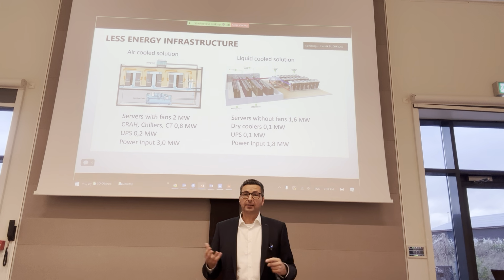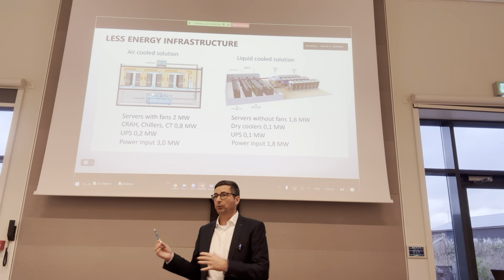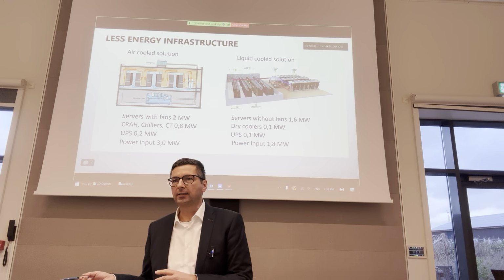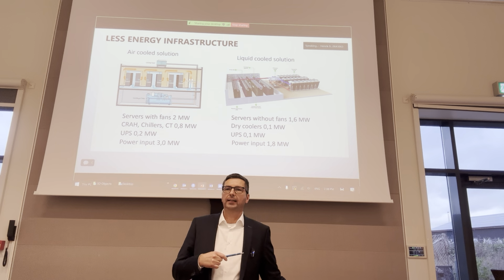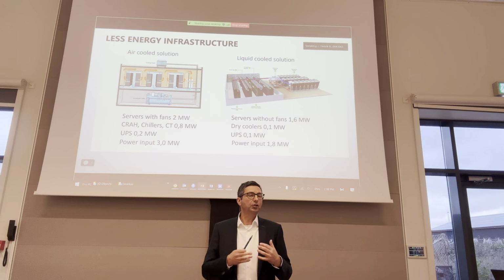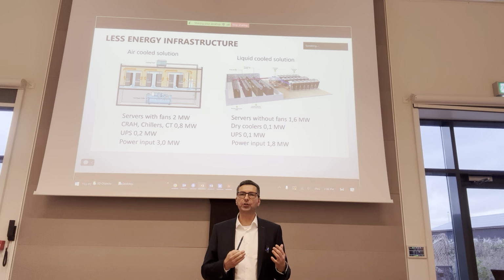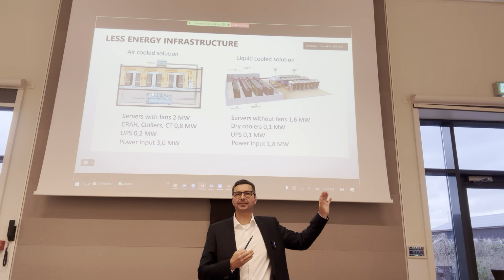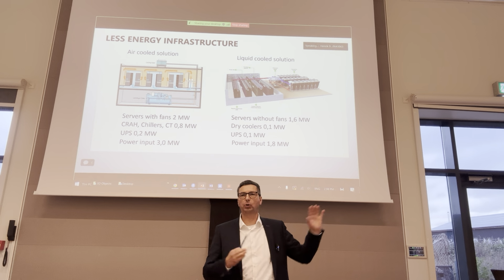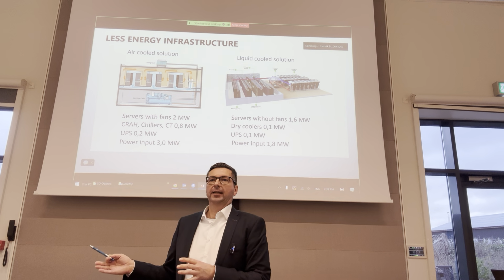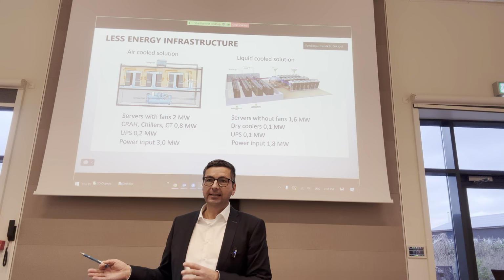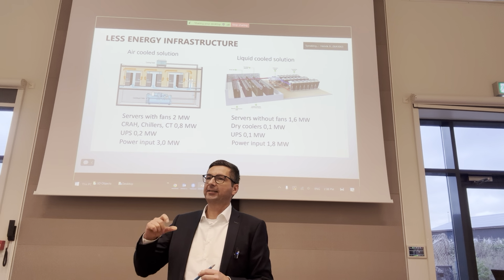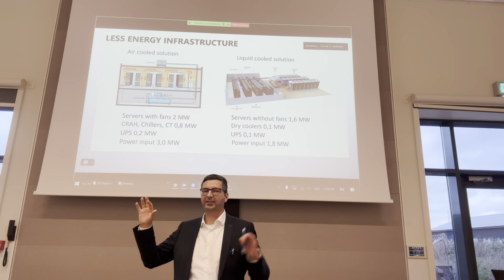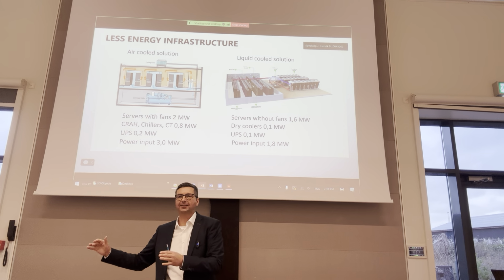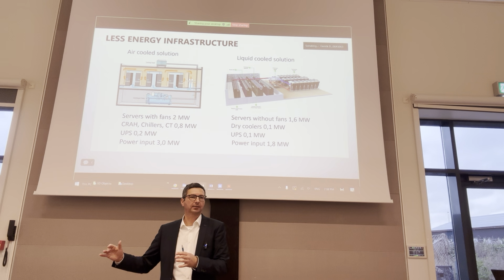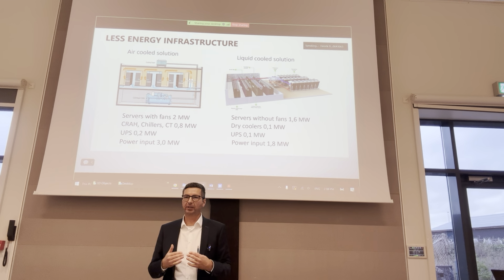You also need UPSs for the setup—legacy needs 200 kilowatts, the other side needs 100 kilowatts. Comparing the whole system, the energy difference between the two setups is 1.2 megawatts less for the 26 liquid-cooled racks compared to the 130 air-cooled racks. That's 40% less energy needed for the new liquid-cooled setup. As a consequence, if all data center sites theoretically switched to liquid cooling, you could reduce energy consumption by 40%.